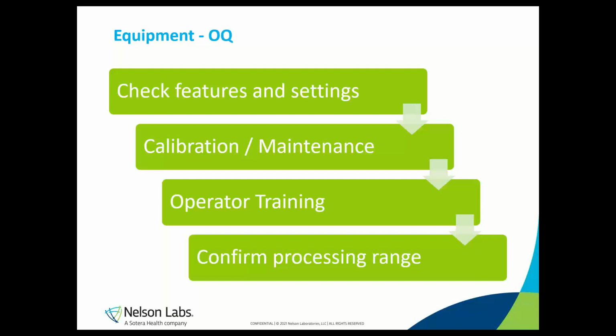The OQ, or operational qualification, is where we test out all the settings and features on the sealer. If the sealer has variable settings, verify that you can change them. If there's safety features, challenge them to see if they work as advertised. In essence, you make sure that everything operates as it should. The OQ also includes the initial calibration of the sealer.